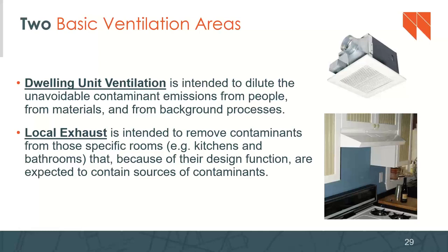It's intended to remove contaminants from the specific rooms. So rooms like kitchens and bathrooms. Some versions of passive house will have you remove it from any laundry areas as well. But the idea here is that because of their design and function, they've got known sources of contaminants, so 62.2 is saying you need to provide, at that local area, at that spot in the home, a ventilation source. So those are the basic ventilation areas.